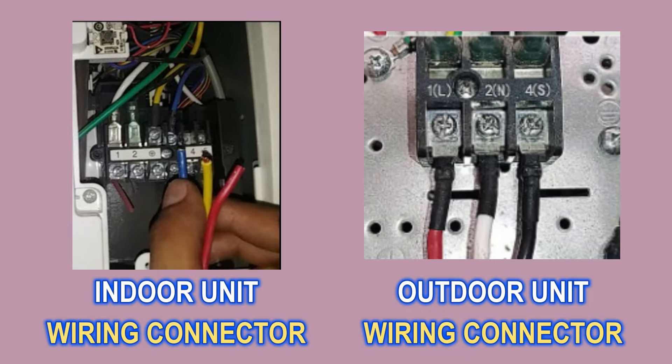The first reason may be the supply wire going to your indoor unit and outdoor unit. Check the connector of the indoor unit and the connector of the outdoor unit — the wire color codes should match. If the same color code wire is not installed in the connectors of both the indoor and outdoor unit, then you will get this error.